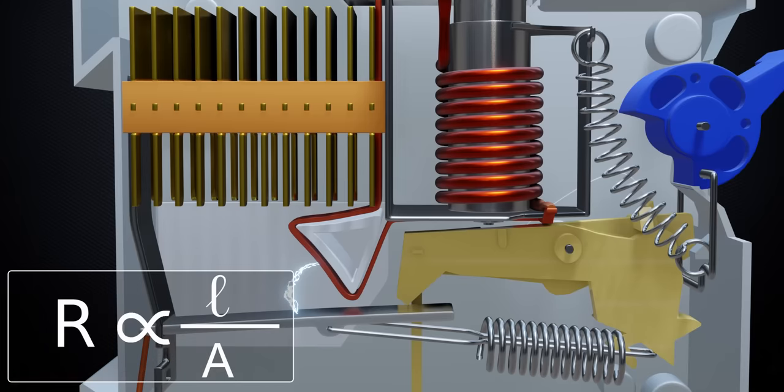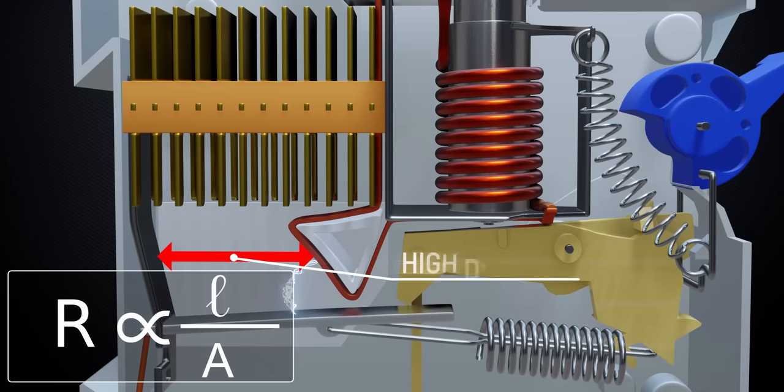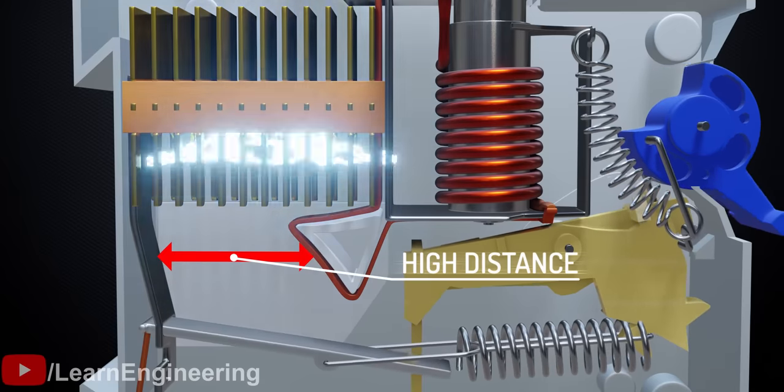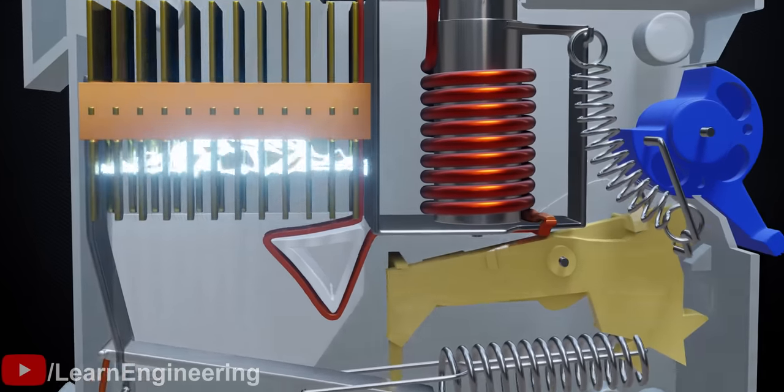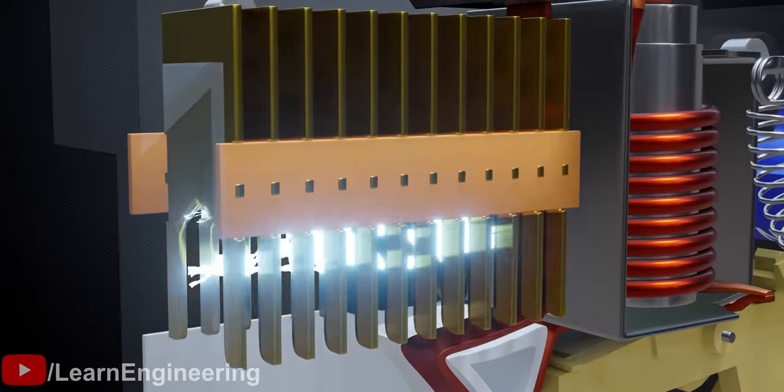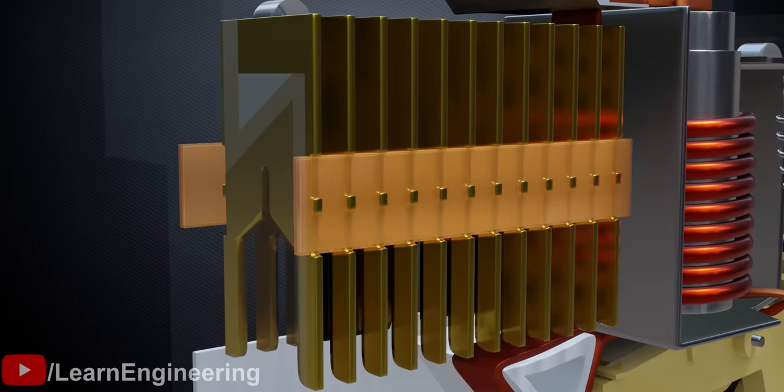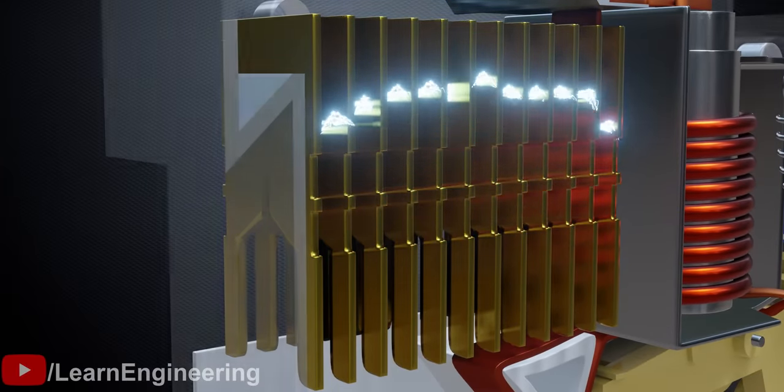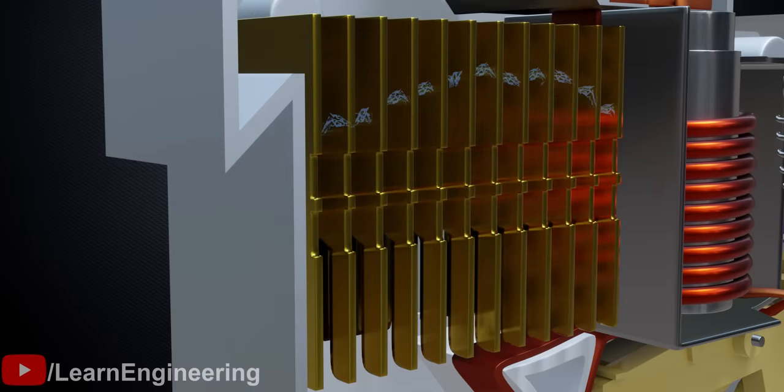Resistance increases with length and decreases with area. Here, we need increased resistance of the current which passes through air, which is why the distance between the contact points is kept high after the circuit opens. Since the air is hot, this arc will be pushed up. Later, the arc is divided into small chunks, thus reducing its area. With increased resistance, the arc dies away at current zero.